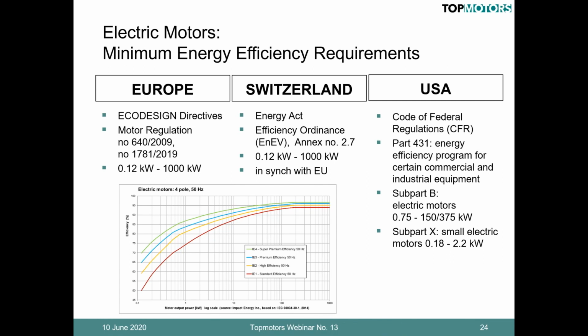Switzerland, not part of the European Union but in Europe, has an Energy Act and an efficiency ordinance, and is synchronized with the European directive. That means it covers the same sizes and all the same types. And then you have the USA. They have a Code of Federal Regulations. There's a Part 431 that defines the energy efficiency programs. And then there's a Subpart B, like Berlin, for the electric motors, that goes from 0.75 kilowatt, that's 1 horsepower, up to 150, and for certain types to 375 kilowatt, that means up to 500 horsepower. And it has a Subpart X, it's really X, for the small motors, which go from 0.18 to 2.2 kilowatt.